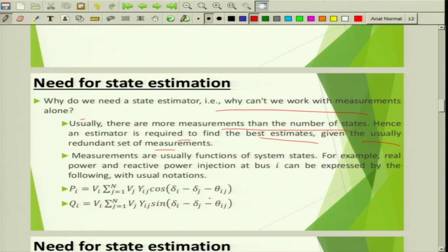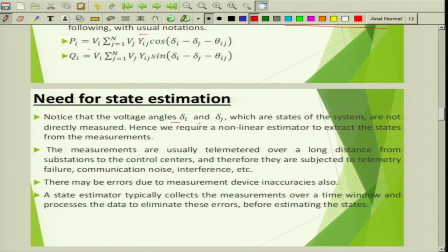Measurements are usually functions of system states. For example, real power and reactive power injection at bus i can be measured, expressed by the following with usual notations. This is very common expression. Active power depending upon the voltage and angle, reactive power is also depending upon voltage and angle here. Notice that the voltage angles delta i and delta j, which are states of the system, are not directly measured, right? Hence, we require a non-linear estimator to extract the states from the measurements.